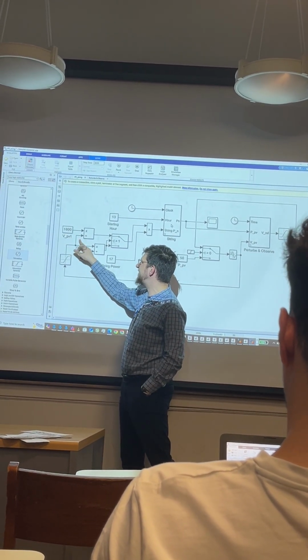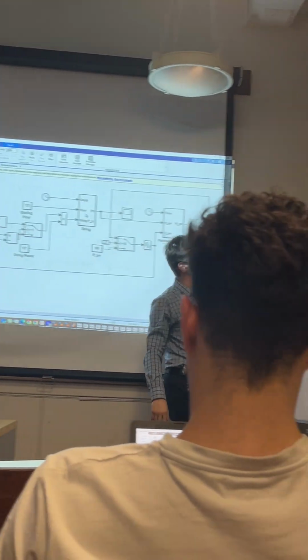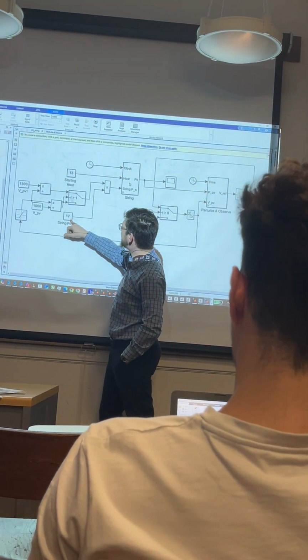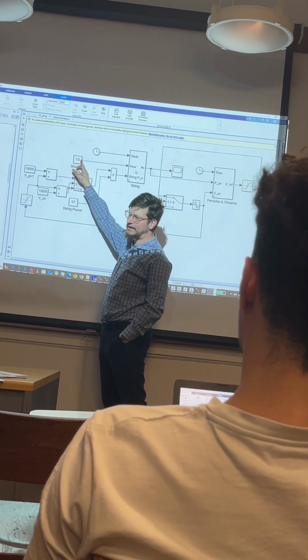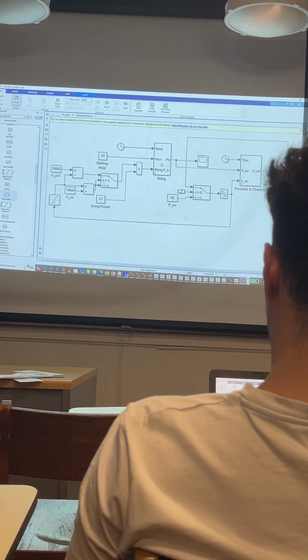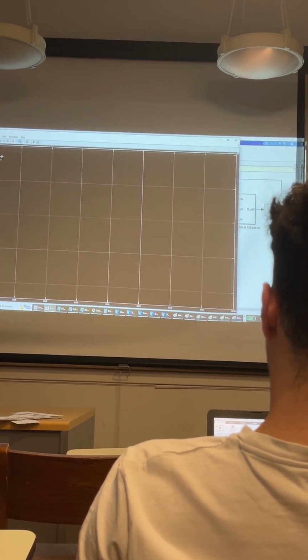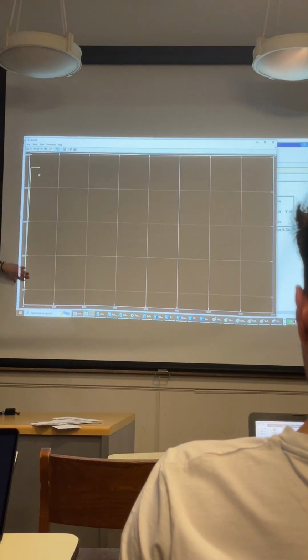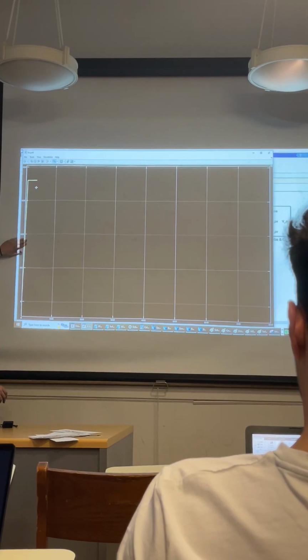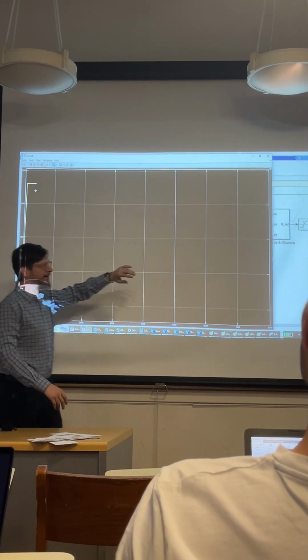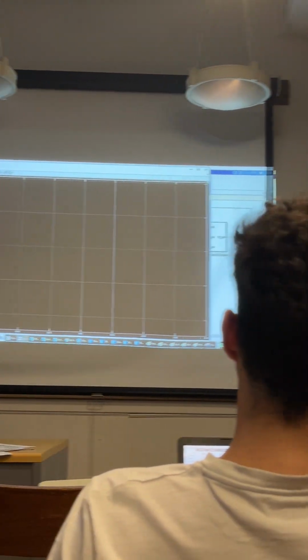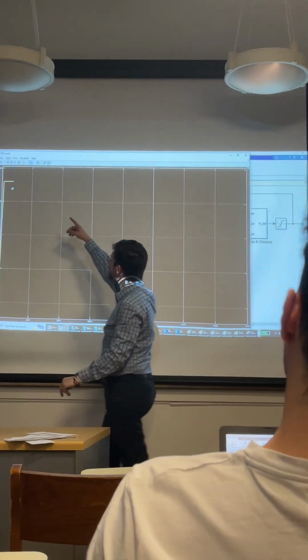Once it exceeds the 1800 volts, let it reduce the power from 17 kilowatts, whatever the time of the day is. So what happened is, the control of the perturb and observe started at a certain voltage, it increased, and once it hit the 1800 volts, it stopped.